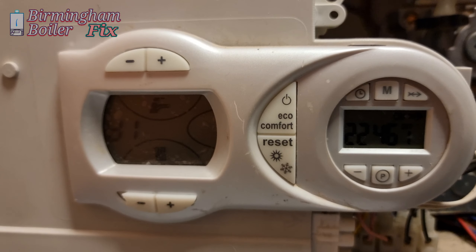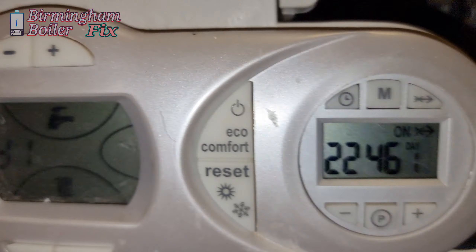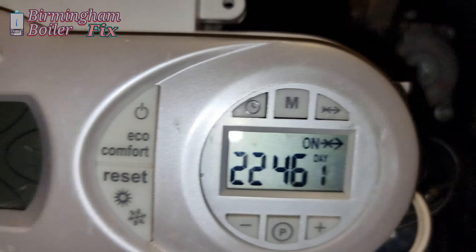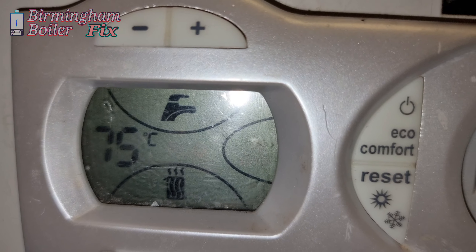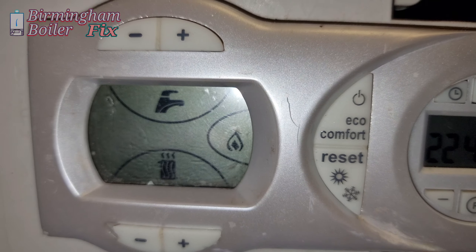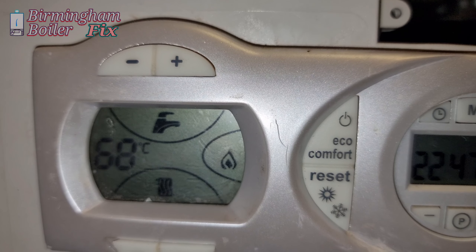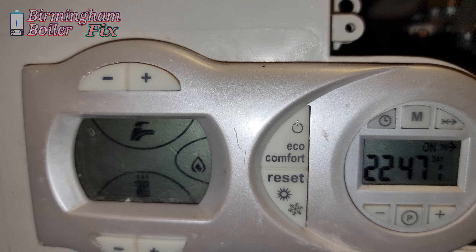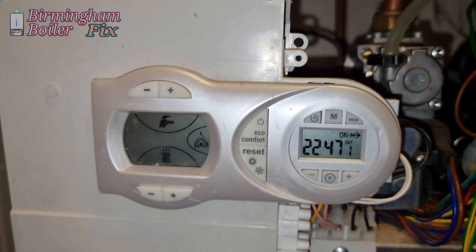Right, we just got this heating going. I've got the heating demand on, I've had the top open so it's going to give you about two to three minutes to turn over. There you go — it's producing some heating. Pump's activated, fan's come on. Make sure you subscribe, share, and like this video. The temperature's fine — it's circulating. The boiler is working, the pressure is fine, and the F37 error is gone too.